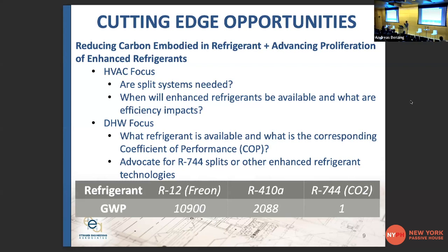The large central stuff making domestic hot water with R744 isn't doing it with a very good COP, and it's not as operationally efficient as maybe a traditional gas-fired system would be, so it might lose. The mini splits, more capable of handling smaller loads, are doing a much better job in efficiency. So for a building with smaller loads, a school like this, not a residential building, we would look to put mini splits in out of the gate.